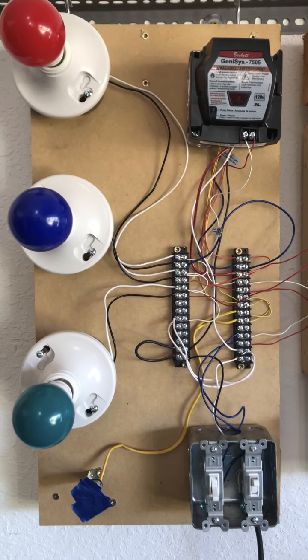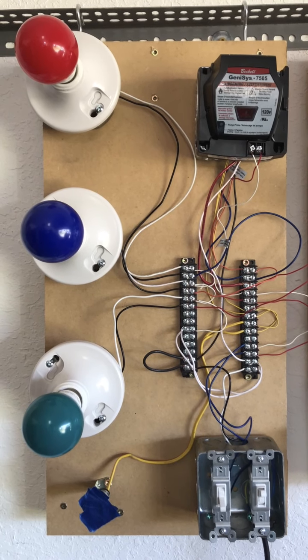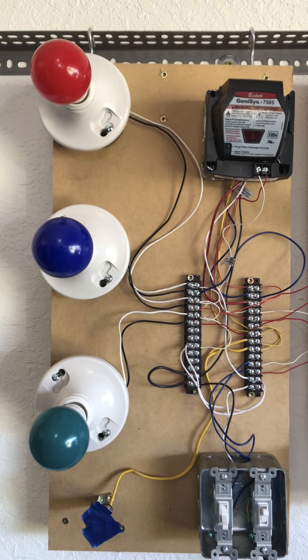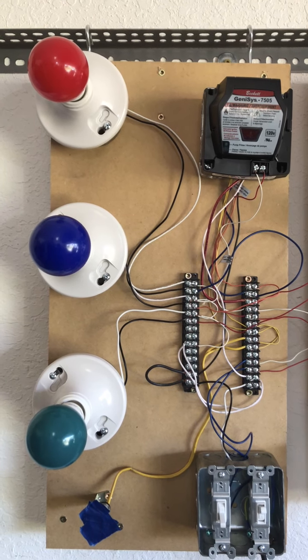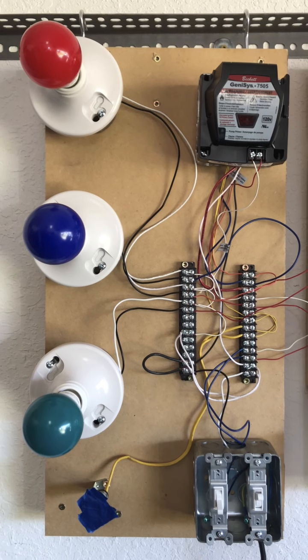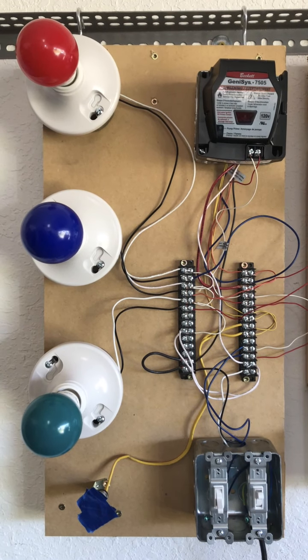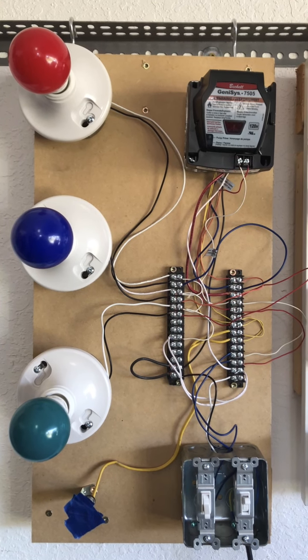So correct operation again is we begin our ignition sequence. We build up pump pressure, we start our igniter, and once my pump is up at full speed and I have pressure on my oil line, based on time, the solenoid opens, we have flame, and the CAD cell eye sees flame. Now let's go through this and see what happens if we don't have flame.